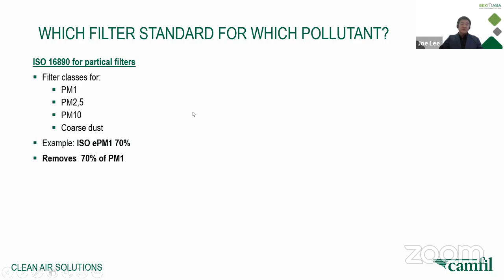Okay, so this will actually determine which kind of filter standard for what kind of pollutants. For here, you can see ISO 16890 particle filters: ePM1, ePM2.5, ePM10. For example, these filters over here are ISO ePM1 70%, meaning they can remove 70% of PM1. So if you have 100 particles in the upstream, there will be only 30 particles escaping from the downstream side with this 70%.